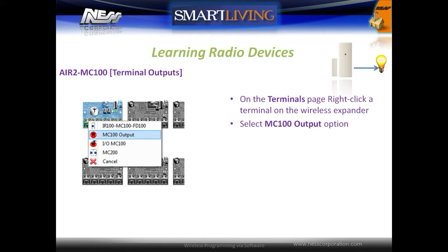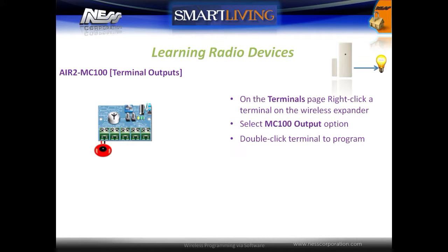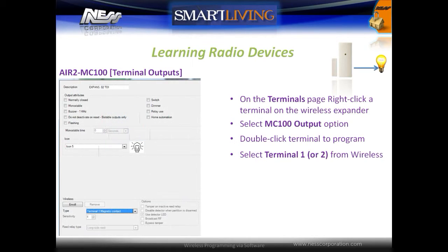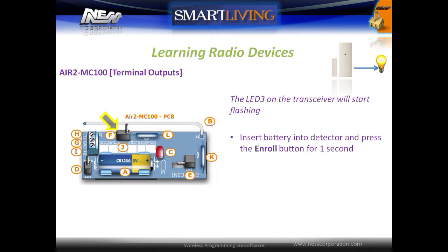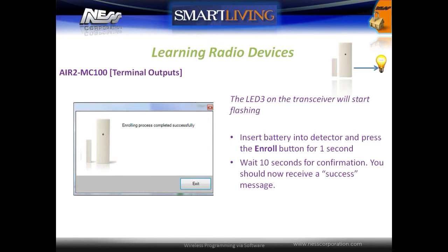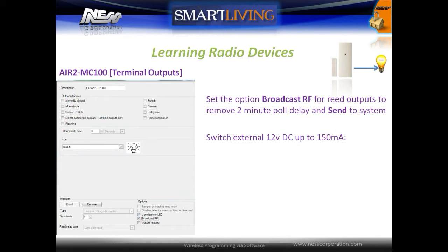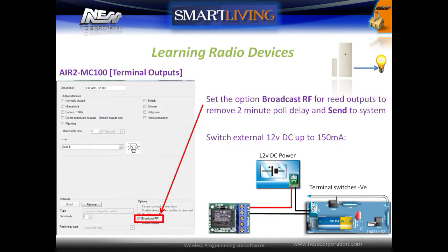To program the MC100's terminal as an output, right click on a wireless terminal and select the MC100 output option. Double click the terminal to open the configuration window. Select the required terminal 1 or 2 from the wireless programming section. Click the enroll button, the LED 3 on the transceiver will start to flash — insert the battery and press the enroll button. A confirmation message should be received after about 10 seconds. Select the broadcast RF option for any wireless output to ensure that it triggers immediately. Wireless outputs do not provide power — they can switch power from an external power source up to 150 milliamps, with the negative of the power supply feeding into the common of the terminals and switched through to the load.